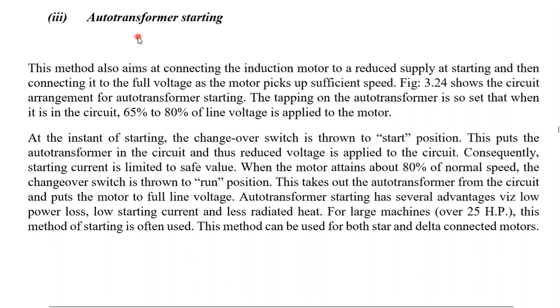In the three-phase induction machine, we have to control the machine by using an auto transformer. That is called a three-phase induction machine, and that's why here also we have to use a three-phase auto transformer. This method also aims to connect to the induction motor to reduce the supply voltage at starting, same as the previous method. So the input voltage of the induction machine can be controlled by using an auto transformer at the time of starting. That is called reduced voltage supply applied to the induction machine.